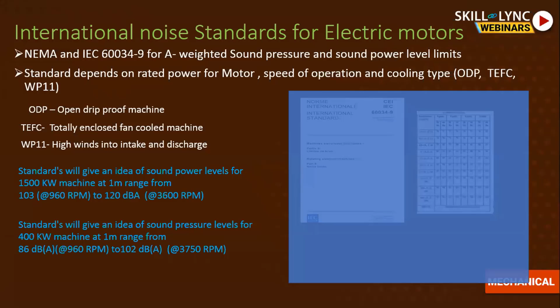It's a big page of standards, but I just wanted to glance at the general range of noise. If you take a 1500 kilowatt machine, which is a very high powered machine, at 1 meter the sound power level with these standards has to be less than 103 dBA at 960 rpm, up to 120 dBA at 3600 rpm. That is the sound power level. For the sound pressure level, with another example of a 400 kilowatt machine at 1 meter, it will be around 86 dBA at lower rpm, around 960, to 102 dBA. So these are the limits for electric motor noise. It has to be within these sound power and sound pressure limits to be qualified or approved for selection.